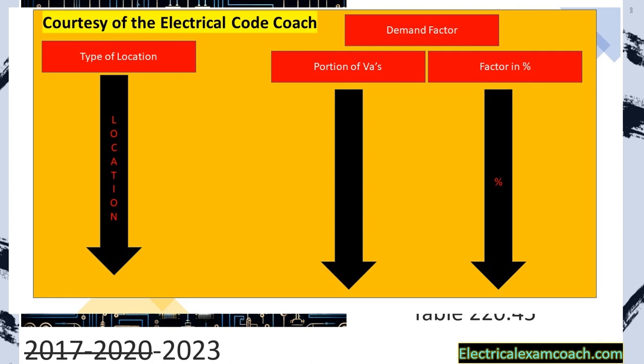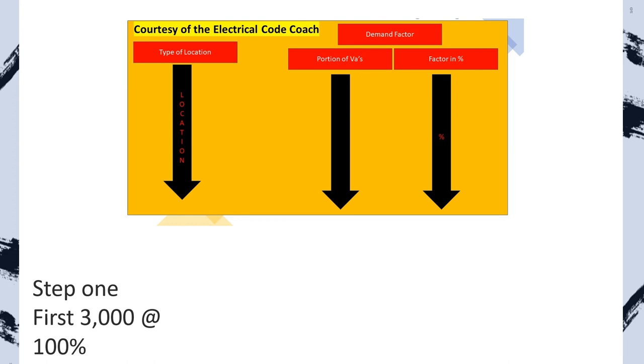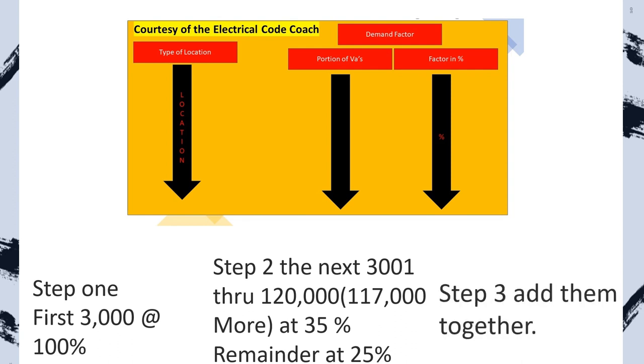Now let's break down how to do the demand factor. When looking at this table, we're going to see a multi-layered demand factor for dwelling units. Step one, we're going to take the first 3,000 VAs at 100%. Step two, we're going to take in between 3,001 through 120,000 — which is technically just another 117,000 more — and we're going to take that percentage at 35%. And then we're going to take anything above and beyond that at 25%.